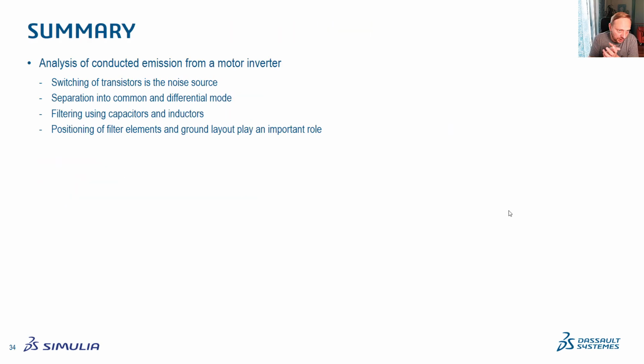So that brings me to the summary. It was almost 45 minutes, so I had some fun speaking. I showed you how to analyze conducted emission from the motor inverter. Of course, the switching of the transistors will be your noise source number one. I separated them into common and differential mode simply to show you that each of them uses a different type of filter.